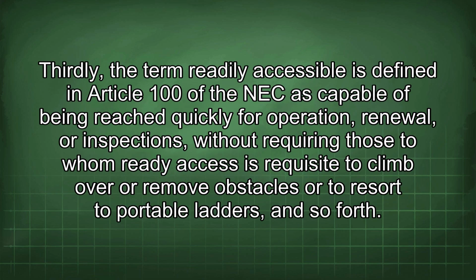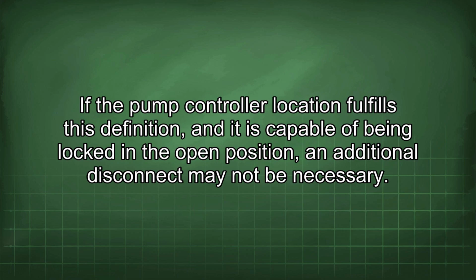Thirdly, the term readily accessible is defined in Article 100 of the NEC as capable of being reached quickly for operation, renewal, or inspections without requiring those to whom ready access is requisite to climb over or remove obstacles or to resort to portable ladders, and so forth. If the pump controller location fulfills this definition and it is capable of being locked in the open position, an additional disconnect may not be necessary.